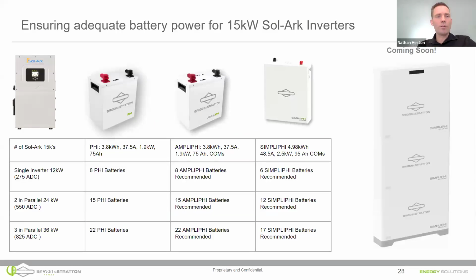So how would we size the Sol-Ark 15k with our batteries? I'm going to get into wiring shortly here, and I'm going to talk about the connections with the Sol-Ark 15k. But I do want to talk about sizing, because that's one of the principal things you have to get right when you're putting a system together. A lot of homeowners want to save money by skimping on the batteries, maybe start with a smaller battery system. You have to make sure that the batteries have enough output power capacity to be able to deliver the 275 amps that Sol-Ark wants when it's at full battery capacity, when it's running 12K out of the batteries. And that's a question we just got, Nathan: do I have to have a minimum number of 4.98 batteries, 2, for example?